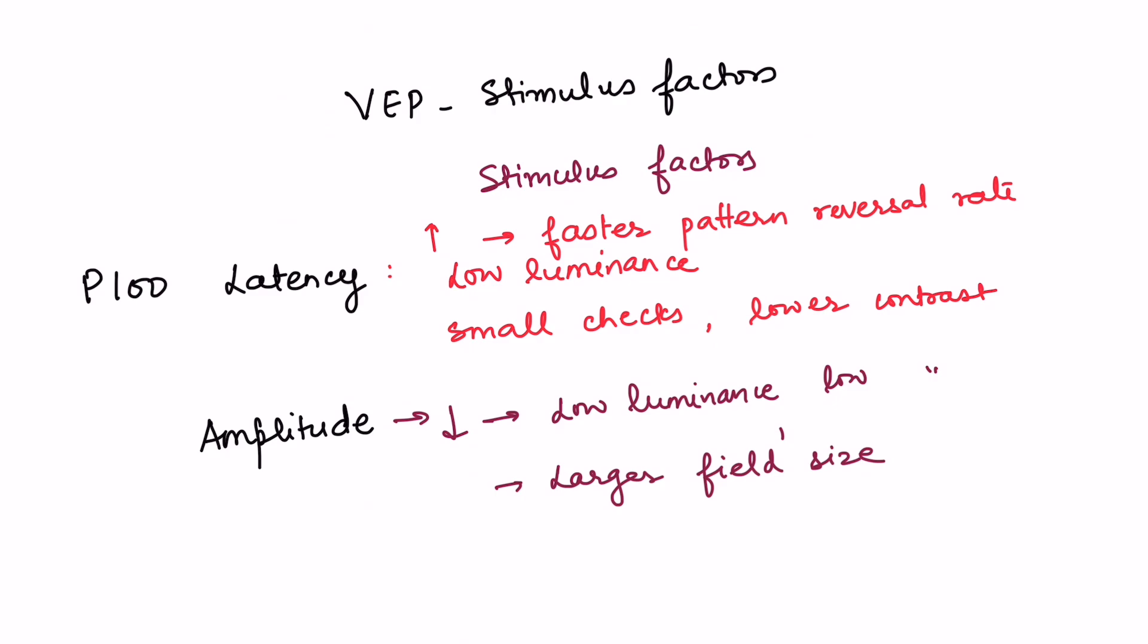Now there are various stimulus factors also which affect the P100 latency and amplitude. We should remember that these stimulus factors need to be controlled properly to get proper P100 latency and amplitude. For example, P100 latency can be increased if the pattern reversal rate of the checkerboard stimulus is faster, if the luminance is lower, or the size of the checks which are there are smaller, or contrast is also lower. So in that case, P100 latency which we will obtain will be more. So we have to be careful that these stimulus factors are consistent as required, otherwise the interpretation will become difficult.